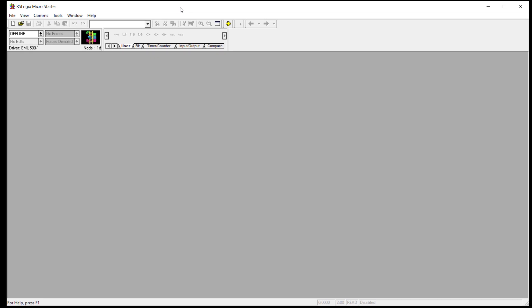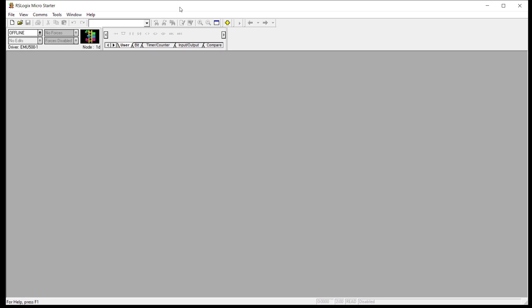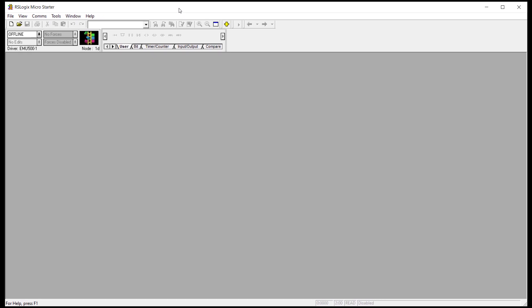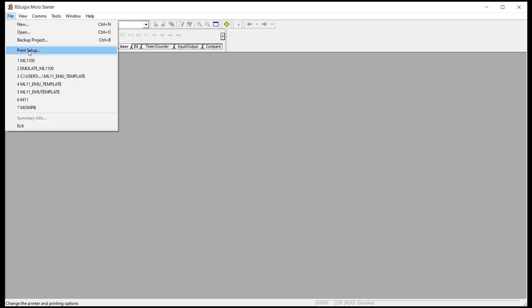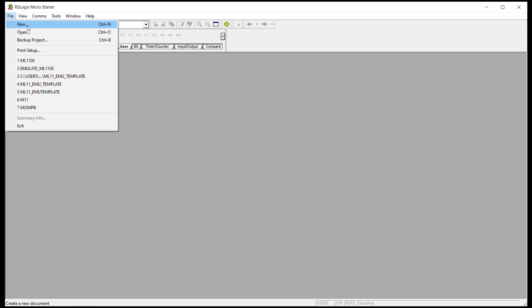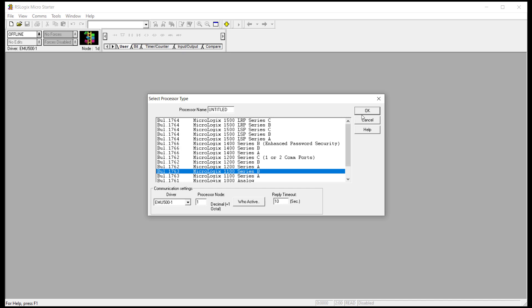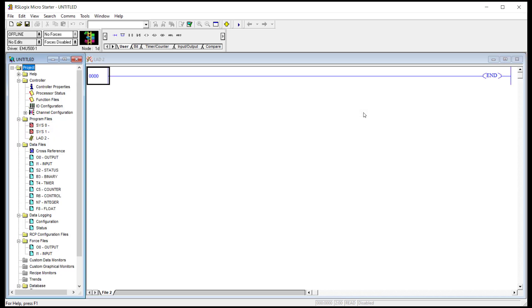Now let's open up RSLogix 500 or Micro Starter or Micro Starter Lite. I'm doing this on dual screens and it's opening up on the other screen, not a problem. We're going to create a program. Now remember that the Micro Starter Lite only supports MicroLogix 1000 and 1100. You have to pick one of those if you're using Lite. And actually, as long as you pick, and we'll just say new, and we'll pick a 1100 Series B.